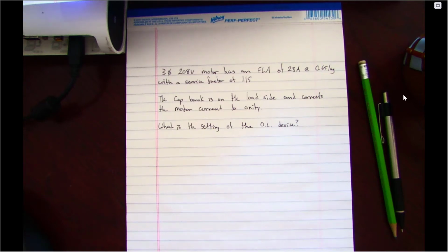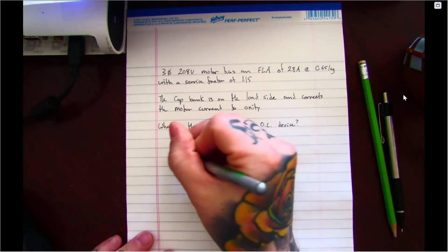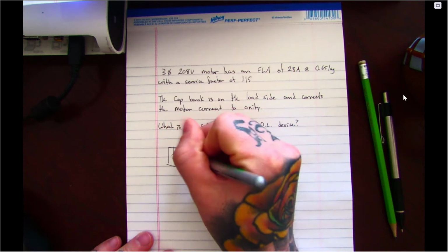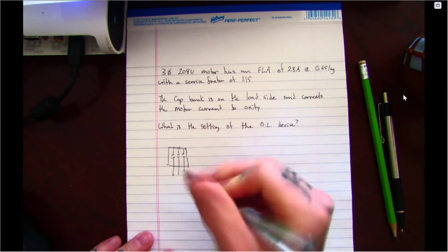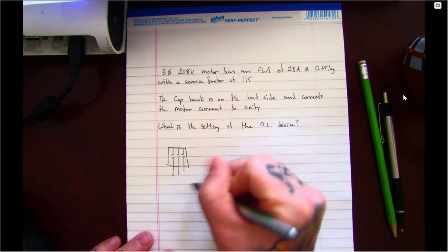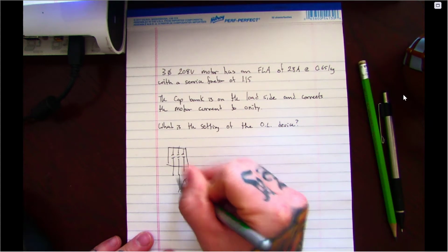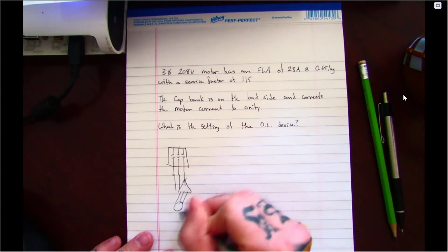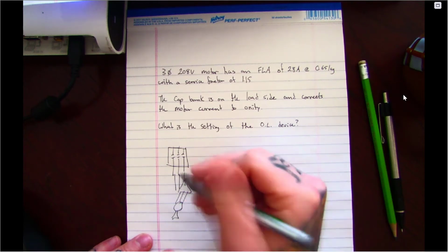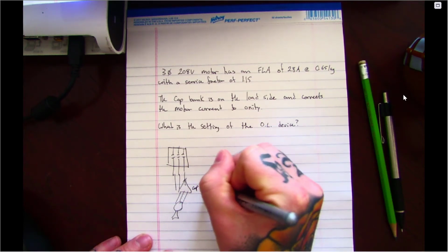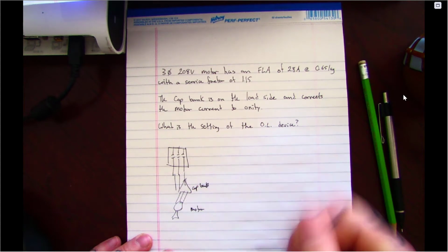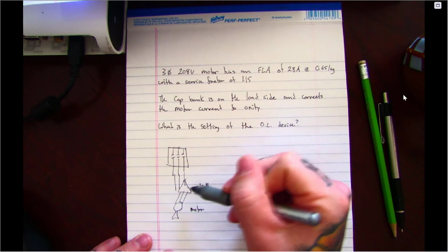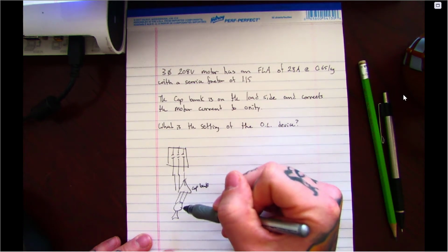So here's a question. We were talking about having the capacitor power factor correction on the load side of the disconnect. So we have our capacitor bank here, and we're going from there to our motor. Okay, so here's our cap bank. Here's our motor. Again, this is a scenario where this acts as a disconnect for the bank, and we don't have to have discharge resistors because they're going to discharge through the motor windings.